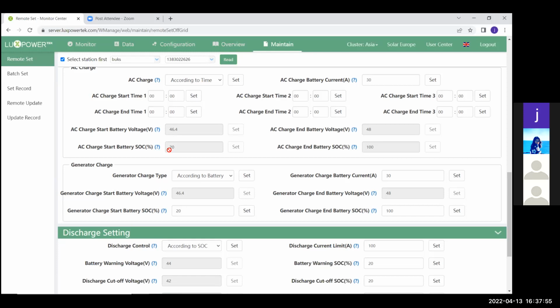So that's also one thing that a lot of people confuse. You can have the AC charge settings set to time, voltage, or SOC. Now you can tell it, during the specific times, if my voltage goes below whatever amount you set, it will start charging to whatever amount you set. So this is if my battery goes below 46.4, it must charge my batteries up to 48. Or if my percentage for a battery that's communicating goes below 20%, it will go up to 100%. Those values you can play around with until you are happy with your AC charge settings.